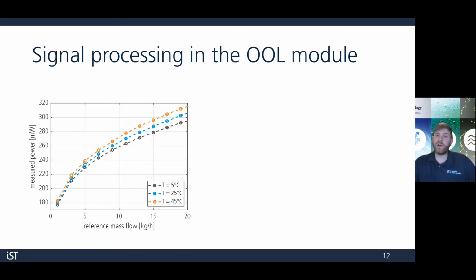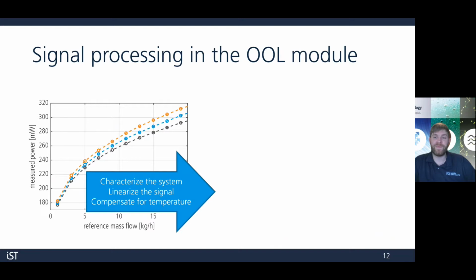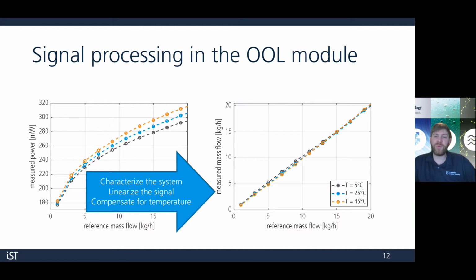Our standard OOL module is calibrated before shipment using water at different temperatures and flow rates. The calibration data is stored on board the module, and the signal is linearized and the temperature is compensated. At the end, our output is delivered as mass flow in kilograms per hour. If you have a different configuration in mind or you're working with a different fluid type, let us know and we can discuss your application in further detail.